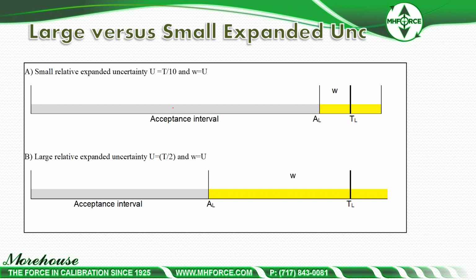And really, it just shows that with a small relative expanded uncertainty, the acceptance interval is going to be a lot larger. So right here, if we look at dead weight, any lab with dead weight primary standards is going to have, more than likely, a smaller CMC uncertainty as far as force goes. So you're going to have much more acceptance interval. And then down here, you're going to have your transfer or secondary standards, so it's going to be a lot smaller.